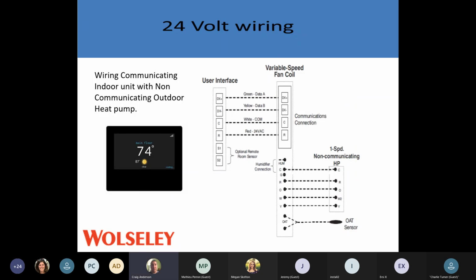Fan coils are a little bit different. We don't need to add a communicating relay to them. Most fan coil control boards will take a heat pump or a two-stage air conditioner. The fan coil is designed for heat pump application most of the time. If we're putting a fan coil with electric heat, chances are that unit is just going to be strictly AC only, or we're putting a heat pump on it. So that board is already wired for a non-communicating outdoor unit.